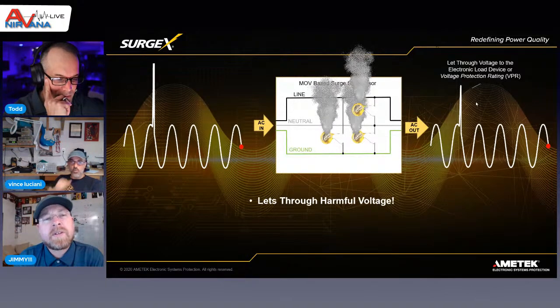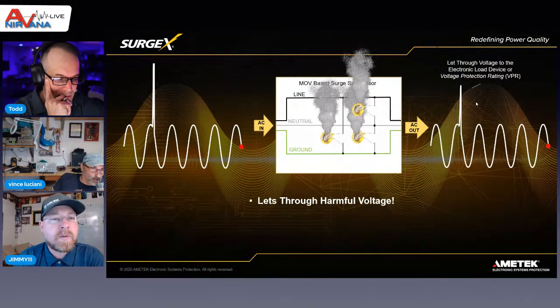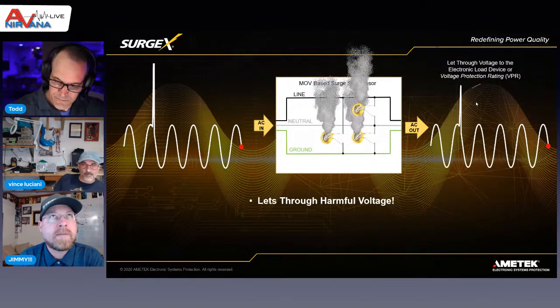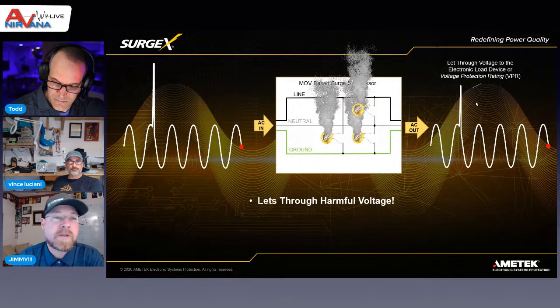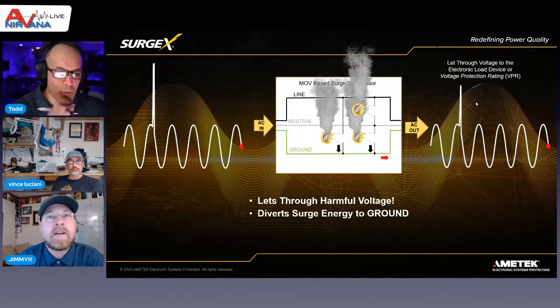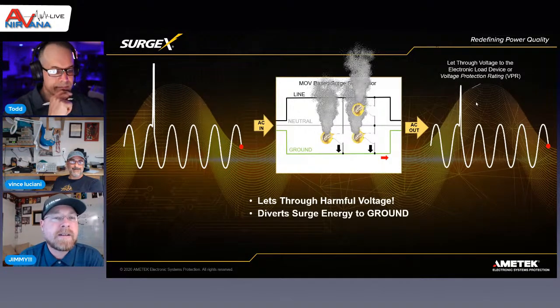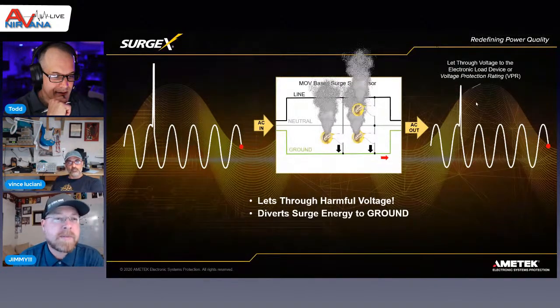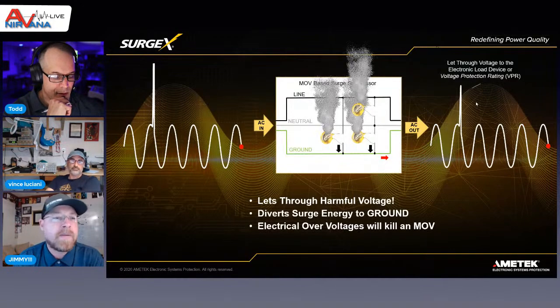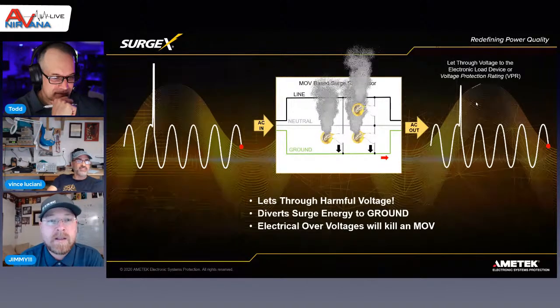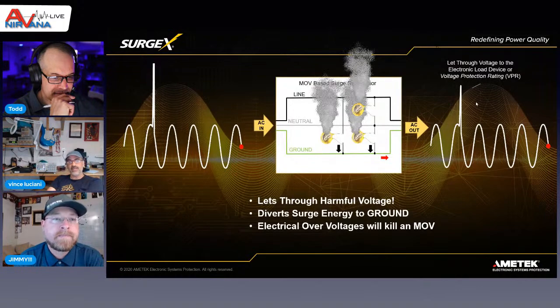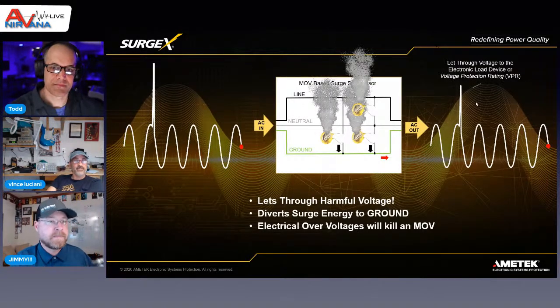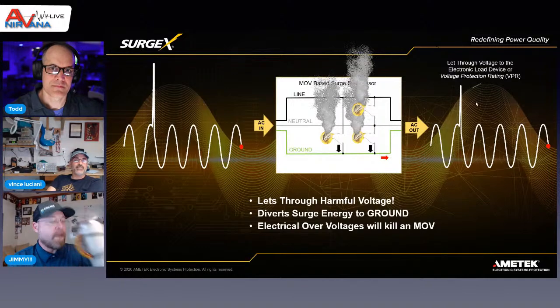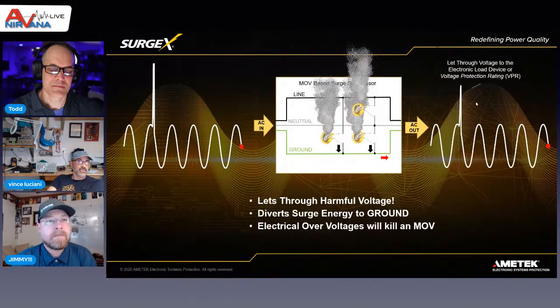We should note the reason we've mentioned 6,000 volts and 3,000 amps is lightning, which could be hundreds of thousands, if not millions of volts. Romex in the home tends to come apart after you hit 6,000 volts, 3,000 amps, so we care about that because it's something we can control for. If it's more than that, we've probably got other issues to resolve. That's kind of the standard the testing agencies have settled on as what is a likely surge that can hit an electrical service.